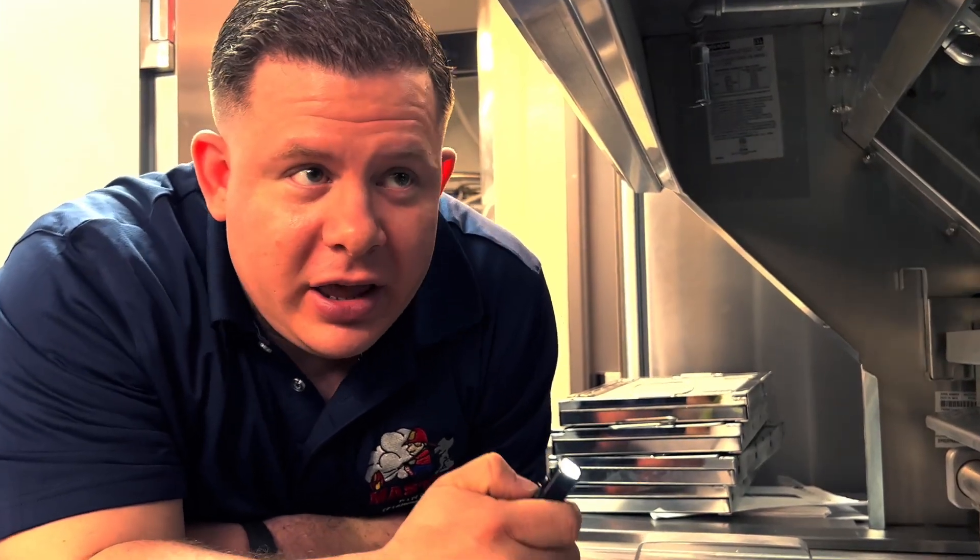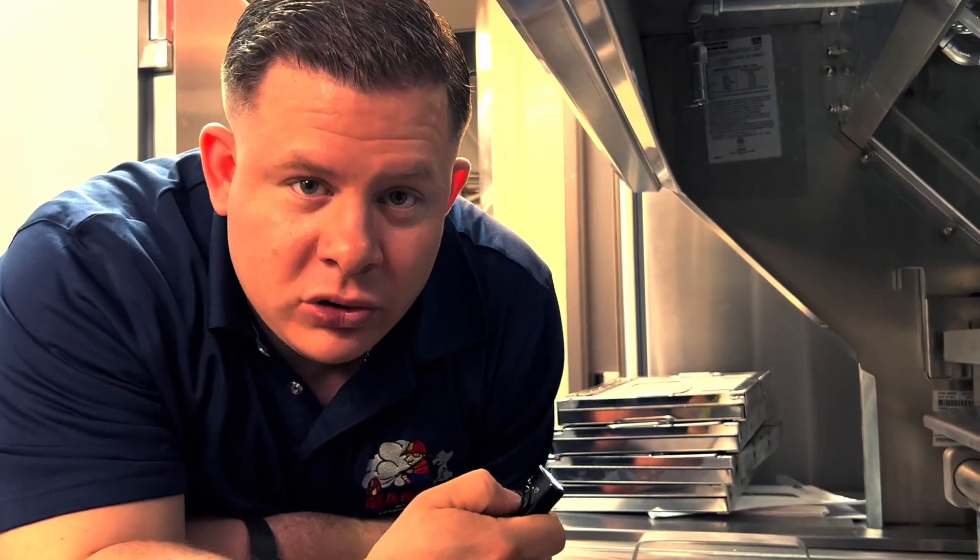Now this is where it all starts — the Ansul system. There are 13 items on this checklist, and it starts with making sure that your system is in the right place, and then you have to make sure that the cylinder, the nozzles, and the piping is all intact. Here are the 360-degree fusible links that will automatically activate your system. Once the system activates, it will distribute the agent through the piping, out the nozzles, therefore suppressing the fire.